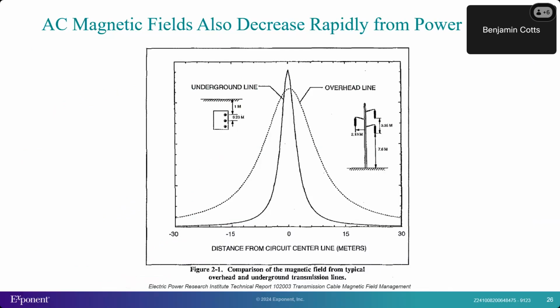That decrease in field with distance from a source is also applicable to power lines. What I'm showing here is how the field level decreases with distance away from overhead or underground power lines. The graph shows the strength of the magnetic field on the vertical axis and the distance away from the source on the horizontal axis, with the center, or zero, being the center line of the respective source. The example here is for an underground duct bank, shown by the inset on the left, and an overhead line, shown by the inset on the right. You'll notice that the maximum magnetic field level directly above the underground duct bank is a little bit higher than that from the overhead line.